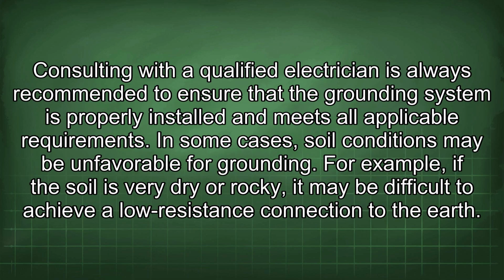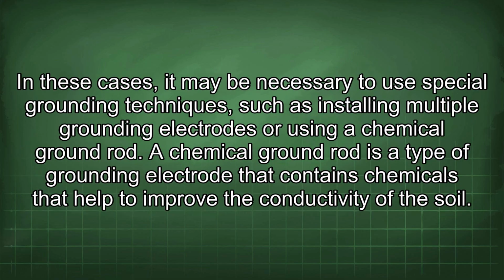Consulting with a qualified electrician is always recommended to ensure that the grounding system is properly installed and meets all applicable requirements. In some cases, soil conditions may be unfavorable for grounding. For example, if the soil is very dry or rocky, it may be difficult to achieve a low resistance connection to the earth. In these cases, it may be necessary to use special grounding techniques such as installing multiple grounding electrodes or using a chemical ground rod.